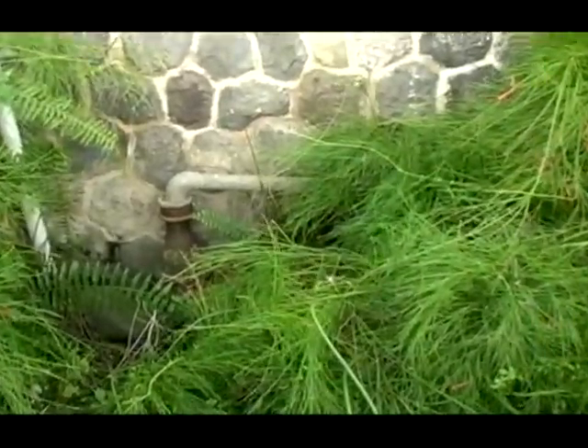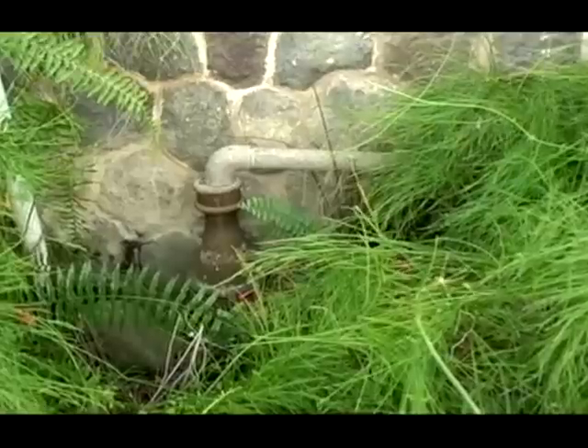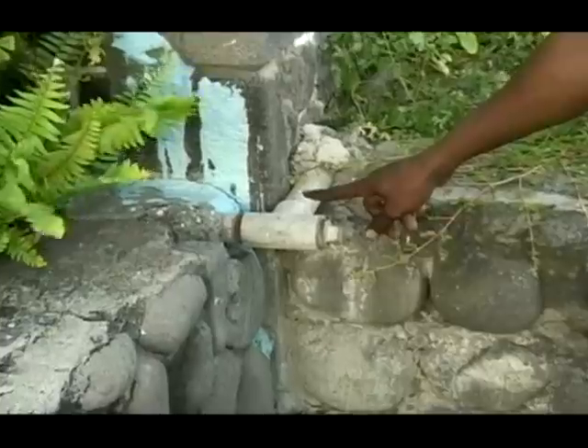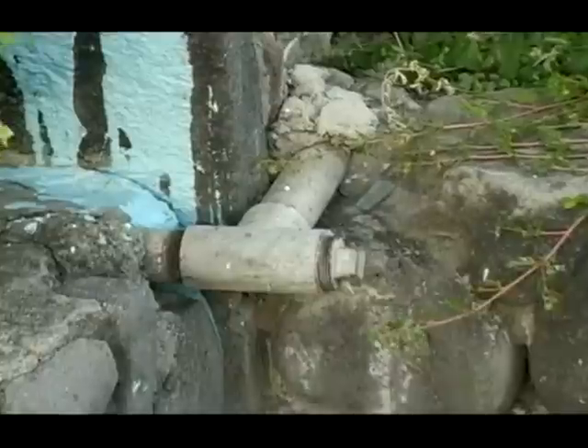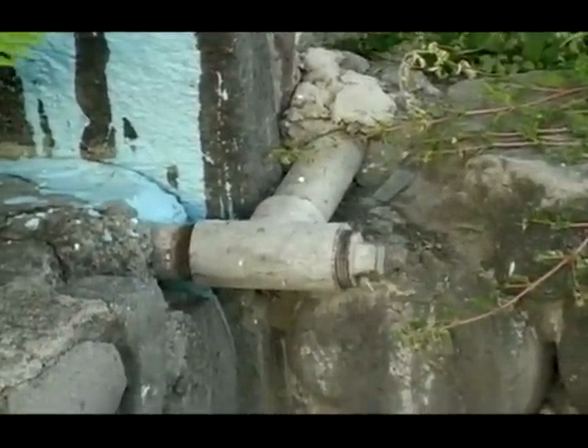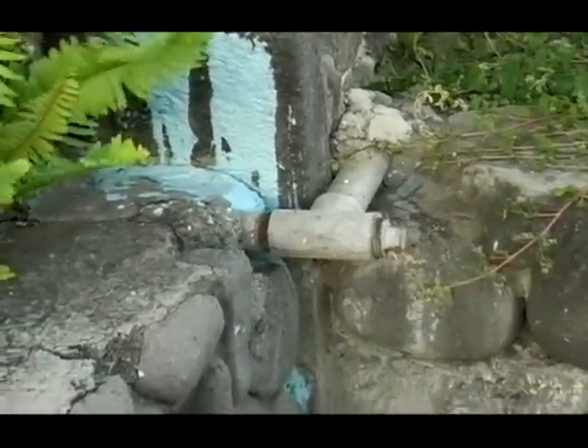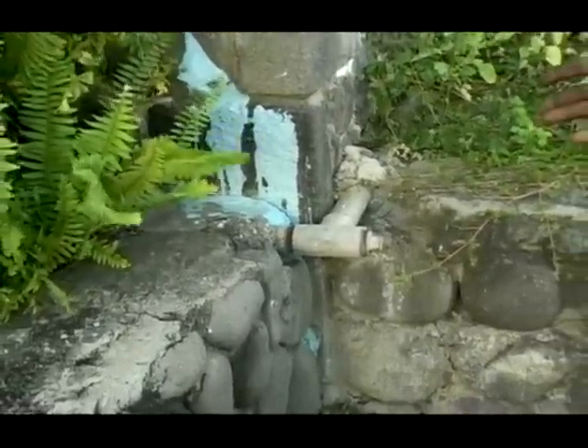The plumbing for the sink should not connect to the plumbing for the toilet — that's a problem that needs to be rectified. It needs a vent that goes all the way to the roof to get rid of the noxious fumes. You would get sewage fumes in this pipe even though it's just a drain line, because it's connected directly to the sewage line. Even though this goes to a sink where you wash your hands and face, sewage fumes can travel back there because these old pipes never had a trap — the S-shaped PVC trap that modern plumbing requires.